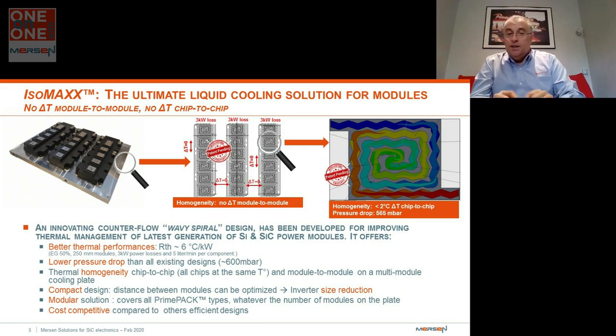And on top of that, there's almost no temperature difference from chip to chip inside the module. So altogether, in addition to the better thermal performance and even lower pressure drop, this homogeneity allows our customers to get the modules even closer to one another, again reducing and shrinking the overall size of the cooling.